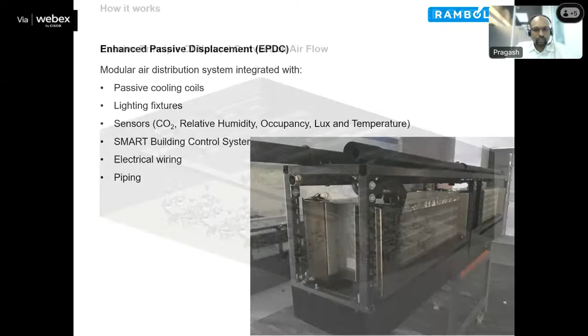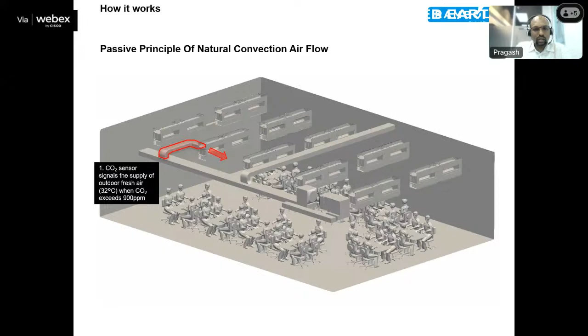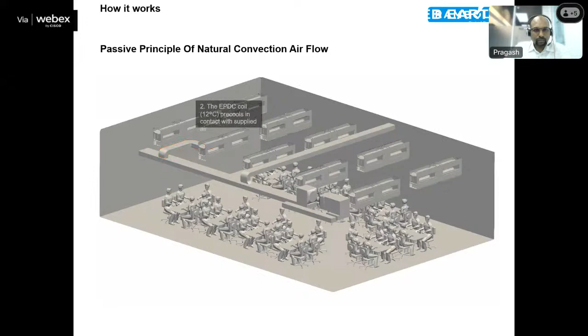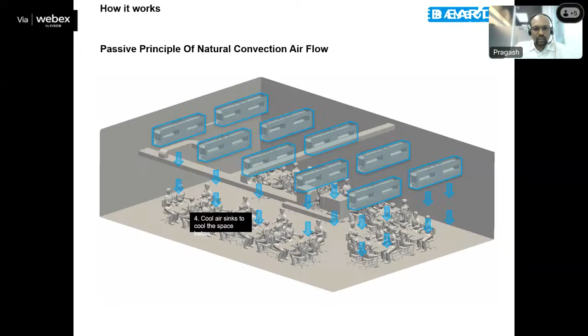You can see the principle here. The fresh air is filtered but not pre-cooled. The outside air is filtered by various filters to remove dust and particles, and then discharged near the coil, which cools it and removes moisture before it blows down into the occupied level. How it works is that there is a double coil displacement unit at the ceiling, where the air is cooled and then directed down a small duct built into the module. I will show you the simulation result later.